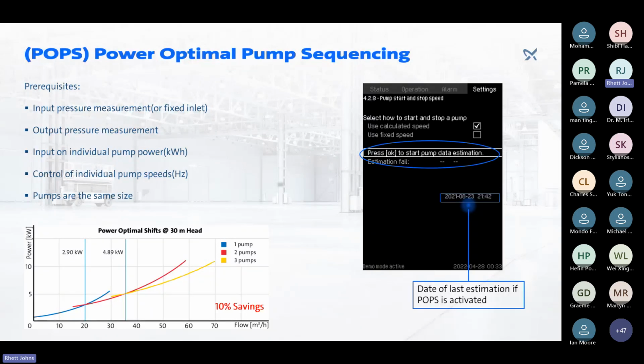Looking at a system like this on the left, we can see that while we could have reached almost 30 meters cubed using one pump, we would be running at a higher power consumption. So at 20 meters cubed, what we can actually do is bring on a second pump, and both of those pumps then ramp down and run at a lower speed, running further back on the curve, at a better efficiency point in order to deliver the flow. And the gains are really quite significant if you compare, looking at 55 meters cubed. Here, a 2-pump system would consume a lot more than a 3-pump system.